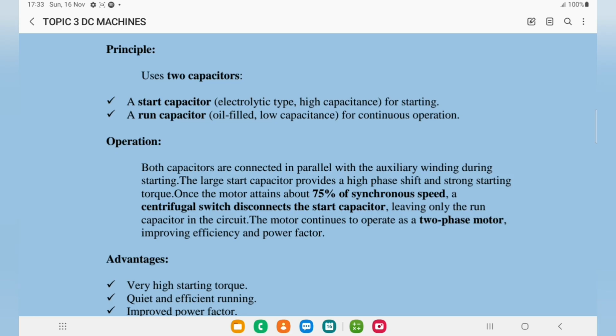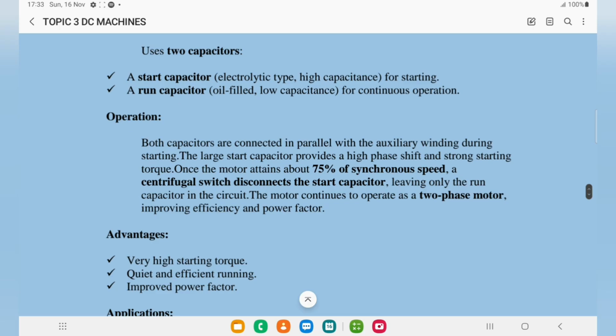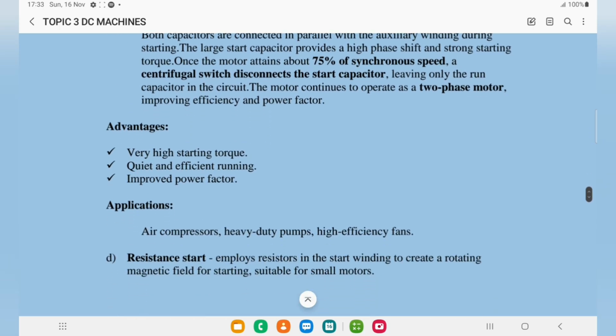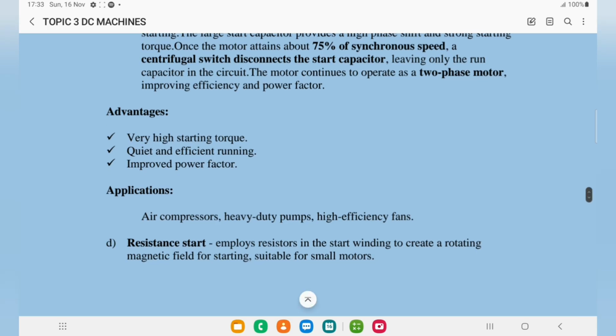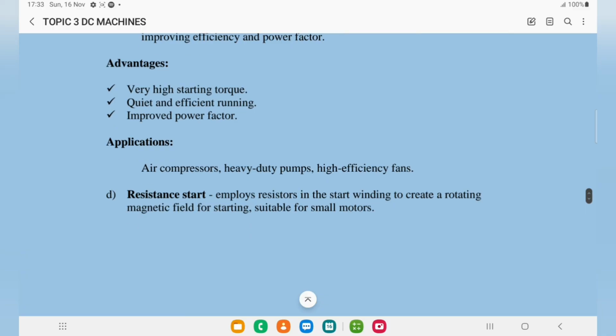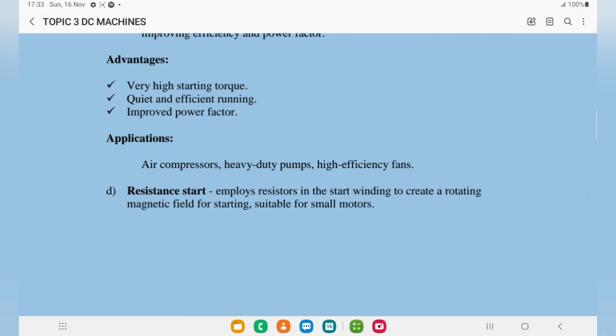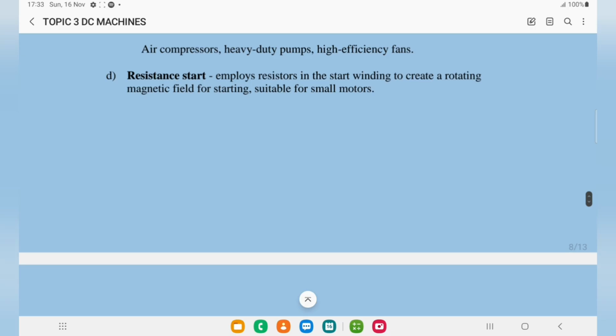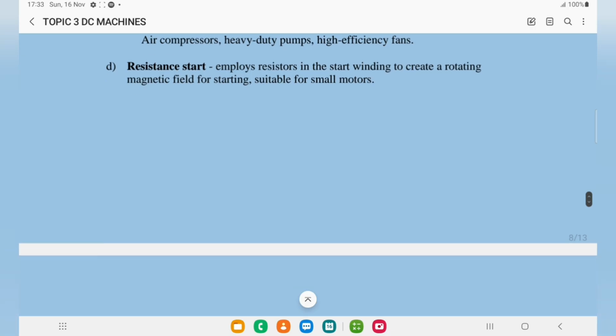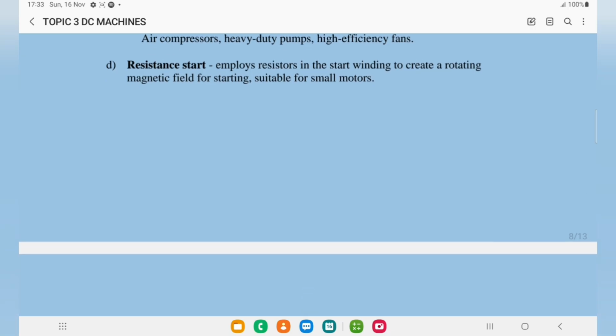So the motor continues to operate as a two-phase motor, improving efficiency and power factor. You shall come to know what happens with power factor when you're talking about rectification. So we have advantages: one advantage is very high starting torque, it's quiet and efficient, improved power factor, and so on. Applications: it can be used in air compressors, heavy duty pumps, high efficiency fans, and so on. Then we also have another method, which is the resistance start.